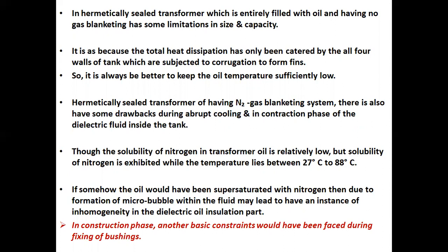A hermetically sealed transformer with a nitrogen gas blanketing system also has some drawbacks during abrupt cooling and in the contraction phase of the dielectric fluid inside the tank. Though the solubility of nitrogen in transformer oil is relatively low, solubility of nitrogen is exhibited while the temperature lies between 27 degrees centigrade to 88 degrees centigrade.